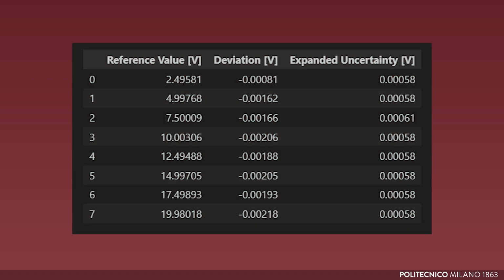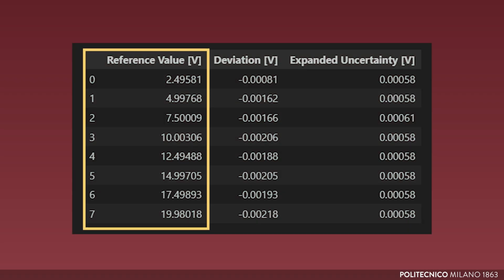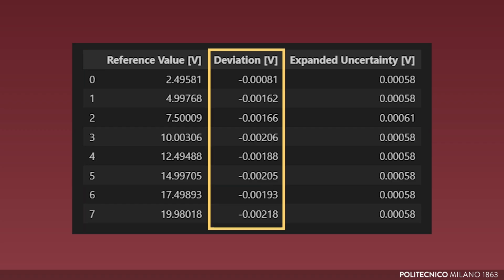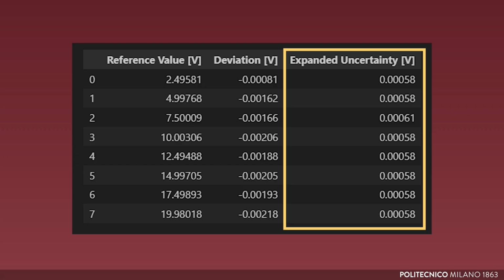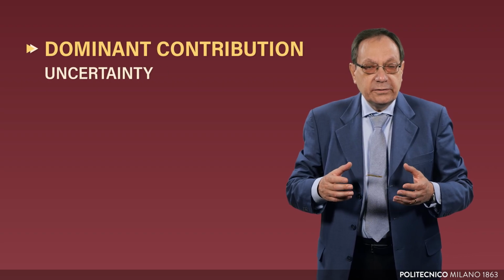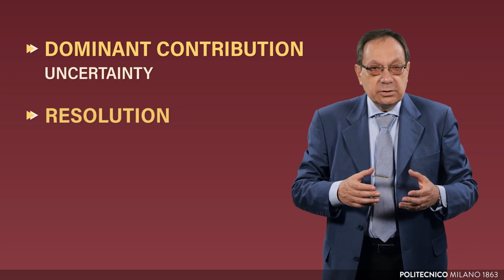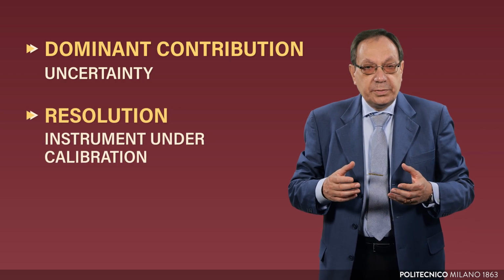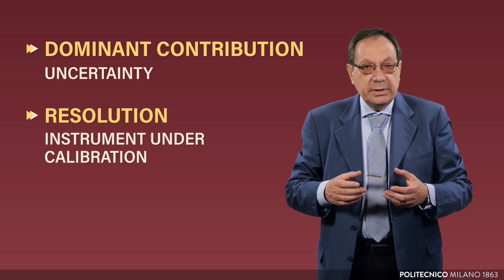The table you see here shows the calibration results. In the first column, you can see the value measured by the reference instrument. In the second, the difference between the value measured by the instrument under calibration and that measured by the reference instrument. And in the third column, the expanded calibration uncertainty evaluated with a coverage probability of 95.45%. As you can see, the calibration uncertainty remains constant. The reason is that the dominant contribution to uncertainty for these instruments is due to the resolution of the instrument under calibration. These operations implement the first step of the calibration process.